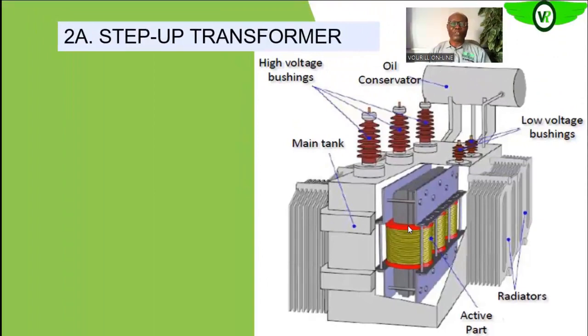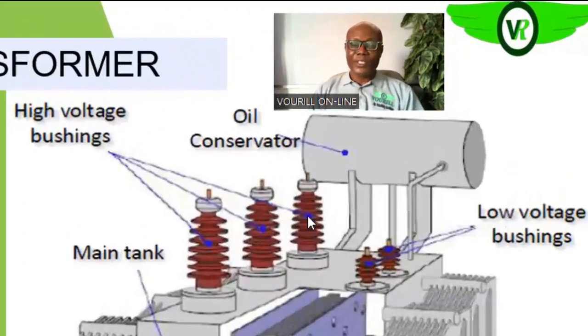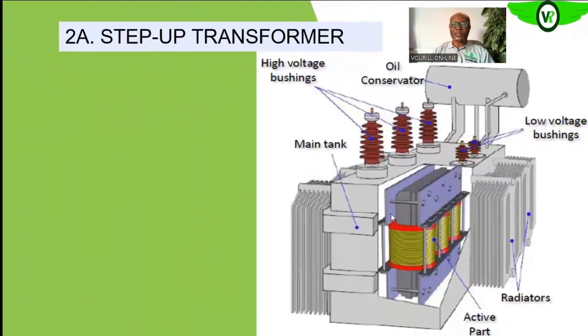But for the transformer to function properly, there are other parts also in the transformer. We have the connection bushings. Since it's a step-up transformer, these are the high voltage bushings, and these are the low voltage bushings. On top of the tank is what is covering the main active part of the transformer, the transformer windings. You also see a radiator-like structure on or around the tank. These are meant for cooling the transformer.